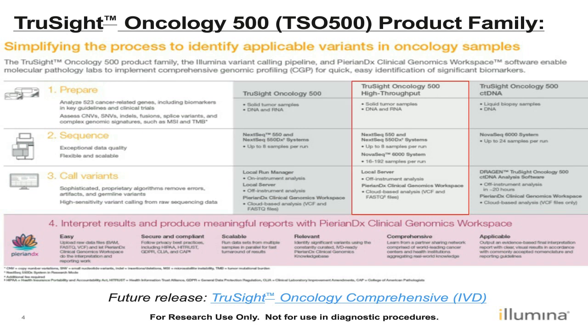Recently released was the TruSight Oncology 500 high-throughput version, which is also for solid tumor samples but increases compatibility with the NextSeq as well as the NovaSeq system to allow higher throughput and higher sample numbers. While running this panel on the NextSeq it's still only eight samples, but on the NovaSeq you can have 16 up to 192 samples. For analysis, it is only compatible with the Linux application — there is not a local run manager version — as well as the PierianDx CGW. It's important to note that while you can run the HT libraries on the NextSeq 500, those libraries are not compatible with the local run manager module.